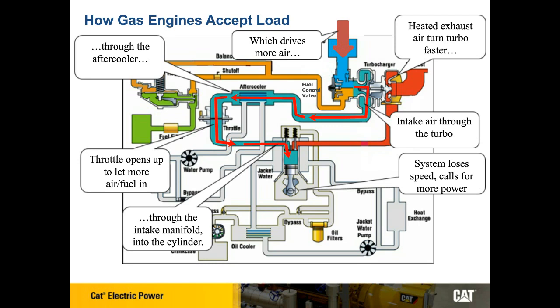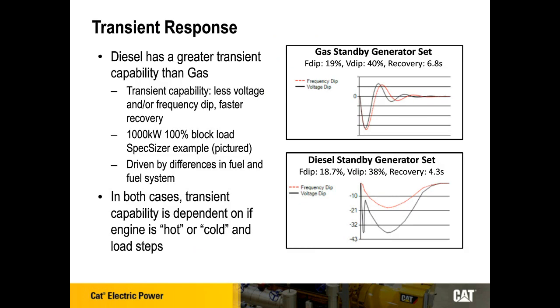So if we look at the actual performance difference between a gas and a diesel standby generator set, these two plots you see on the screen are out of the Caterpillar SpecSizer program. They're both for a 1 megawatt generator set, and both for a 100% block load. The top is for a natural gas generator set, and the bottom is for a diesel. With a 1 megawatt, 100% block load, the gas standby generator set and the diesel have basically the same dip, about 19% frequency dip. The voltage dip is also really similar, 40% for the gas standby and 38% for the diesel standby.